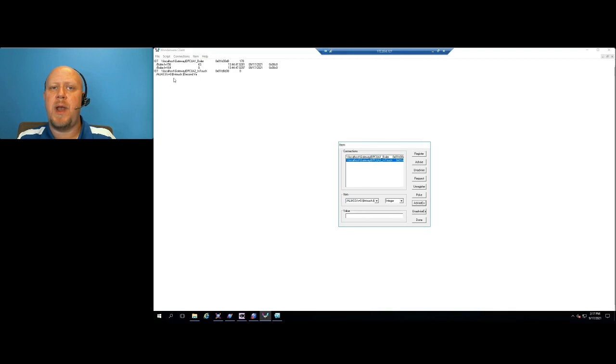You'll notice that I'm not getting good quality on this one. I get a 04 instead of a C0. That's because the name of my tag was too long. So what I can do in this instance is utilize the alias3 alias name or namespace and just do alias3.myIntouchTagName.value. So in this case, it's going to be alias3.$2.value. When I did that, you can see that I do have a good value.